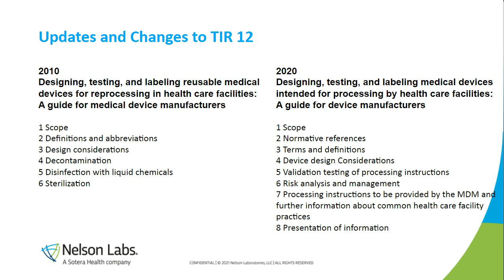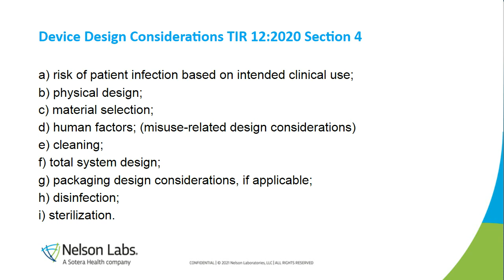We are going to start with Section 4, Device Design Considerations, which was previously Section 3. This section was expanded to include A, risk of patient infection based on clinical use, G, packaging design applications, considerations, E, cleaning, H, disinfection, and I, sterilization. Remember, as a device manufacturer and designer, it is key and critical to consider these aspects during device design rather than discover the hard way that the material you've selected is not compatible with the sterilization method you want to use. Please learn from the experience of the writers of this document.